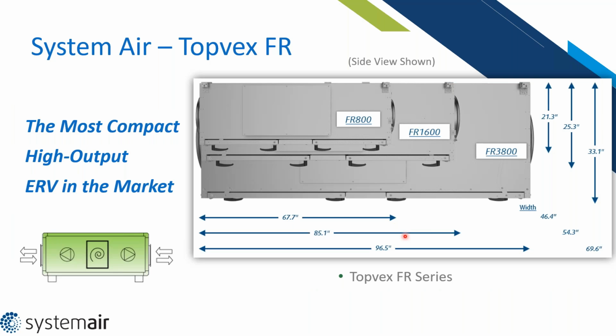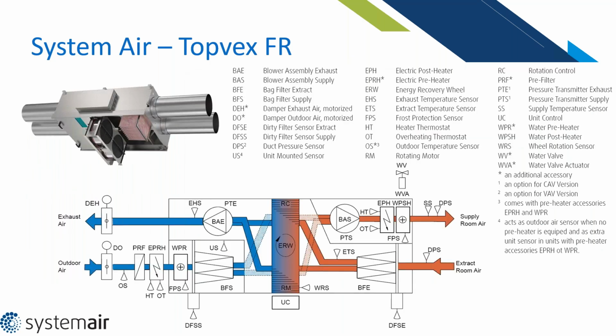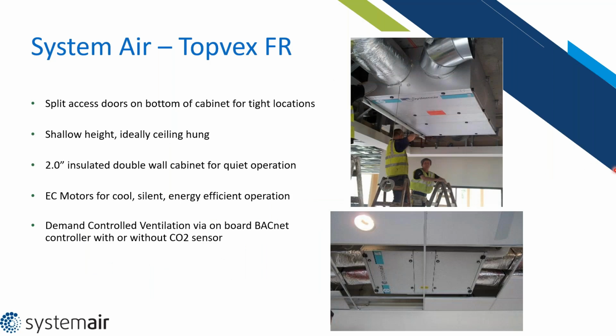Now this is the Topvex. The other one I showed you; this is the one that goes in the ceiling. It's the most compact, high output ERV in the market. For a 4,000 CFM unit that can go in the ceiling, 33 inches depth is really not that bad. And all access is on this double access door right here. So pretty good overall. Here is another component list, similar, where the fans are robust. The model I'm showing right here has a dual wheel system, not a dual wheel in the typical DOAS reference, but actually in line. So the airflow goes through both of these wheels. That's what gives it the very high effectiveness that I was talking about earlier. Here's an example of what it looks like. This is the biggest one, and here's the access I was talking about. You'd be able to access both sides from the drop down right there.